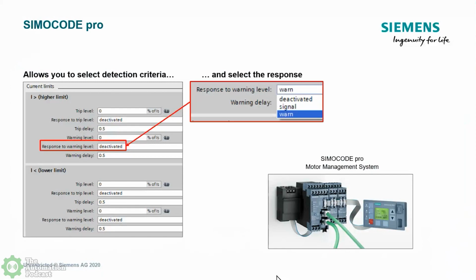So what I'm showing is within the SIMOCODE, and if you remember in the slide previously, I talked about having some logic. This could be my high and my low that you usually put in as code in the PLC or the DCS system. So that means that the SIMOCODE can stand alone in a pump panel all by itself, and you can set up high and low current limits and have it trip on maybe a pump that's running some sprinkling systems, or maybe a small water pump for culinary, but it has all the capabilities of what you would use in a PLC for small projects standalone, or you can set these up to work in conjunction with the PLC or DCS system.